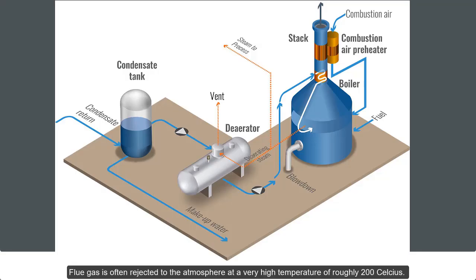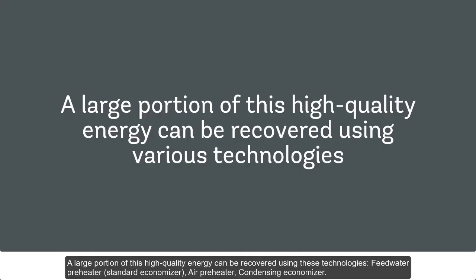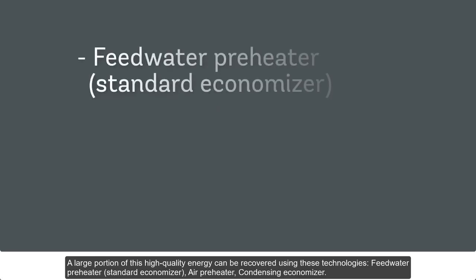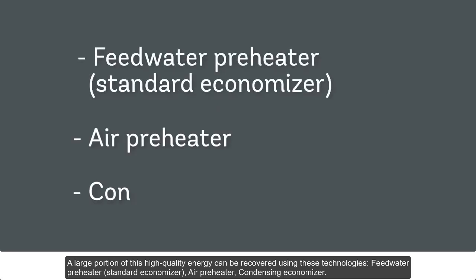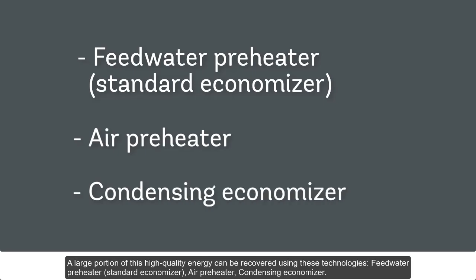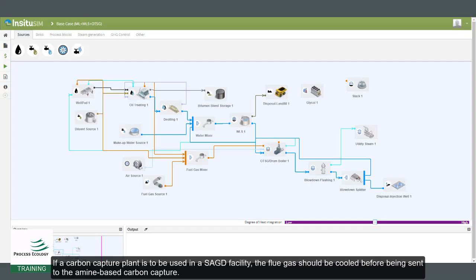Flue gas is often rejected to the atmosphere at a very high temperature of roughly 200 Celsius. A large portion of this high-quality energy can be recovered using these technologies: feed water pre-heater, standard economizer, air pre-heater, and condensing economizer.